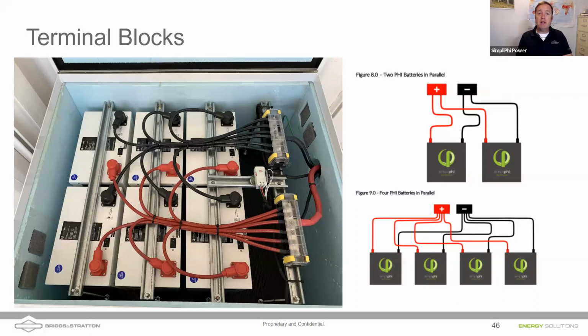It's important to always run your batteries in parallel such that you run conductors of the same gauge and same length to a common terminal block, and then run one single home run. In this example, this cable is kind of the same length as this other cable, how it's wrapped around. That means you're not getting any resistance differential on these battery cables, and not causing one battery to work harder than the next.